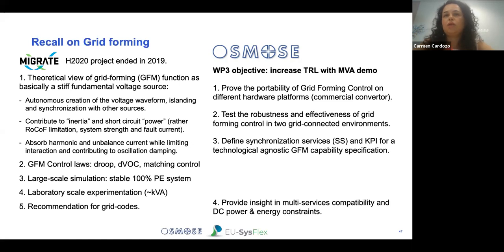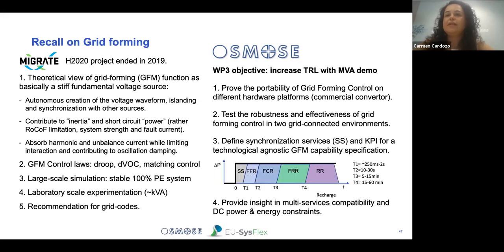So the idea in this Work Package 3 was to build an MVA scale demonstrator to increase the TRL of the technology. By this we mean to prove that we can put the controls proposed in the Migrate project into commercial hardware, a converter, without any need for a special design of the converter. Then to test the robustness and effectiveness of the grid forming control in grid connected environments, and at the end to define synchronization services and, above all, the key performance indicators - how to measure these services in a technology-agnostic way.